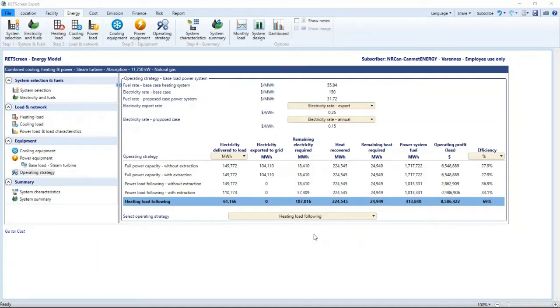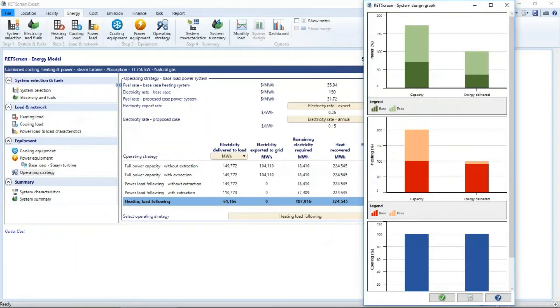By clicking on the system design, I can now review the basics of my design, which is to follow the heating load. The steam turbine cogeneration system is going to provide 36% of the electrical energy, 90% of the heating energy, part of the heating load being an absorption chiller.